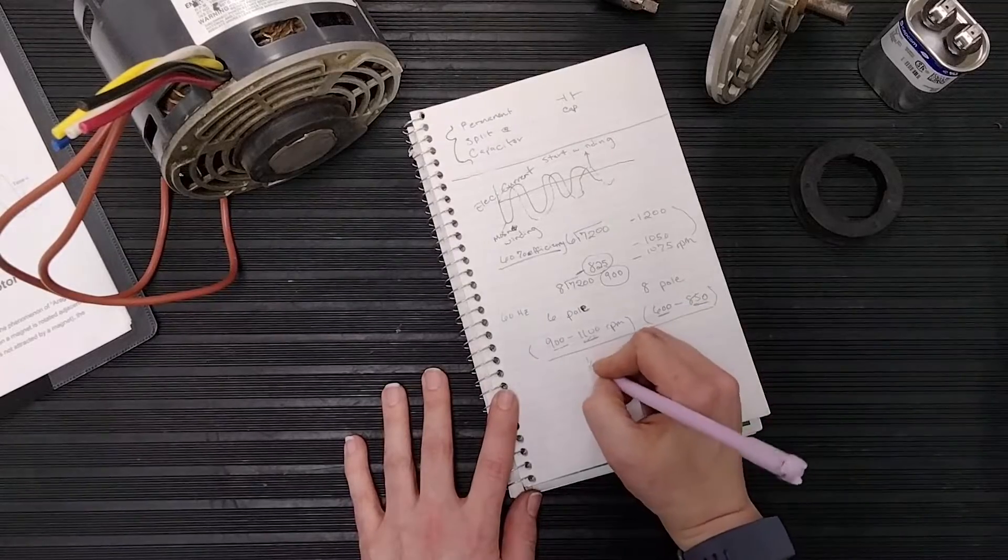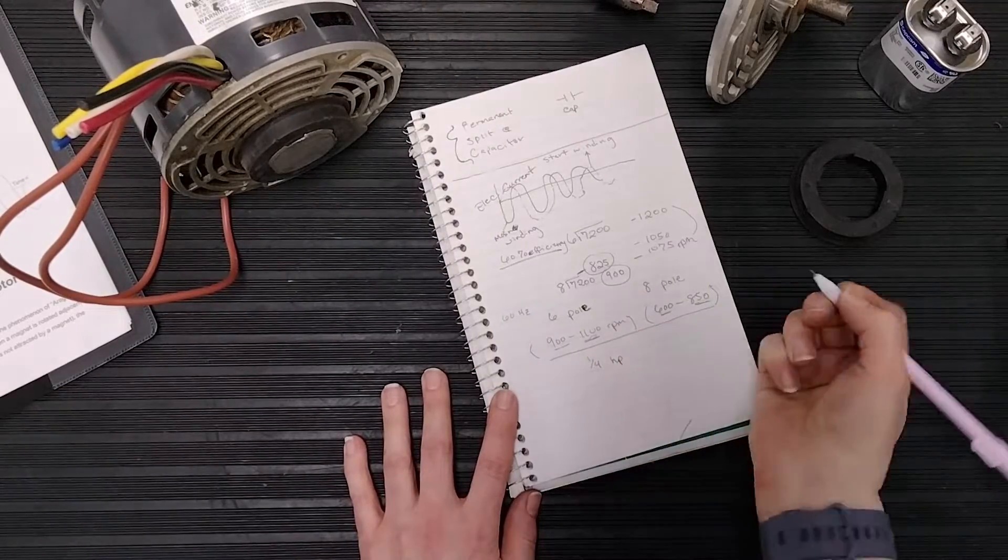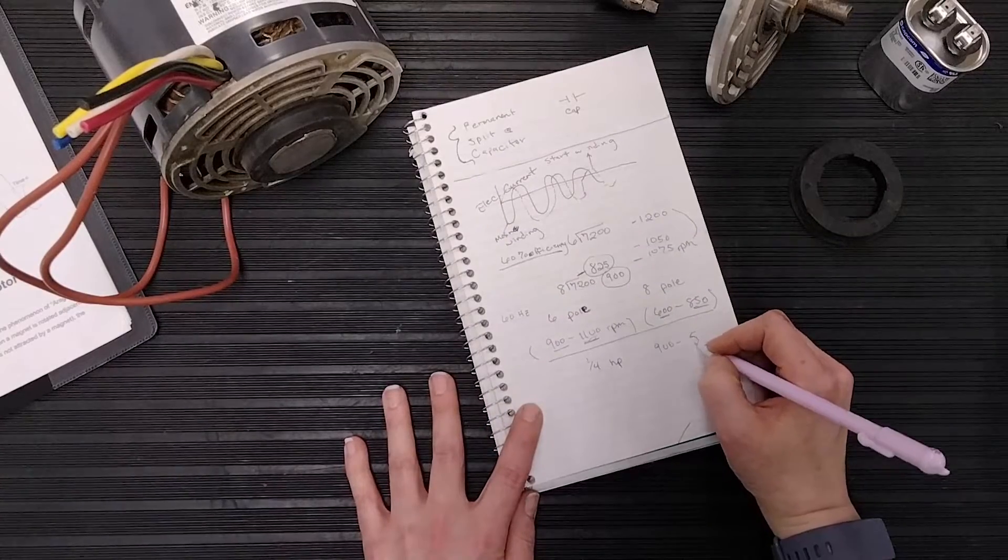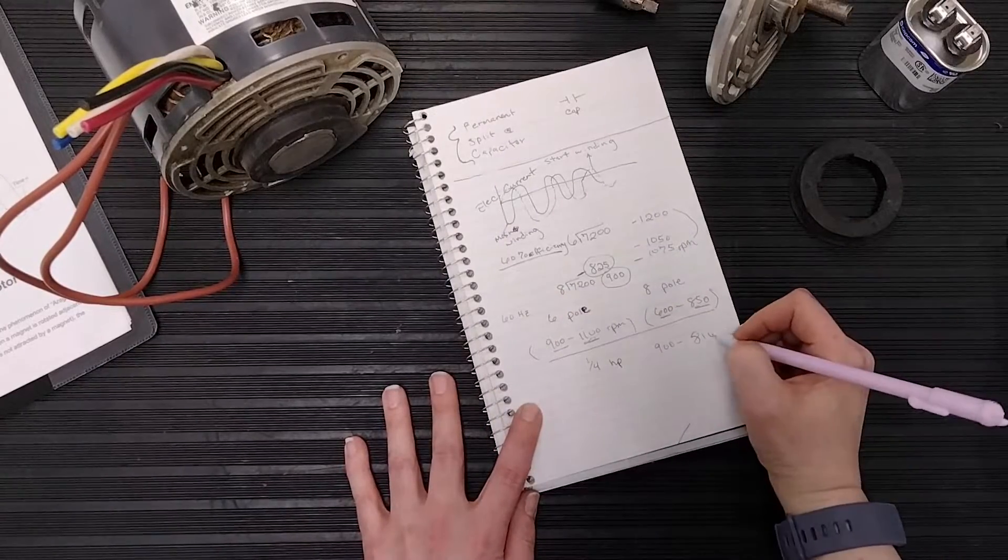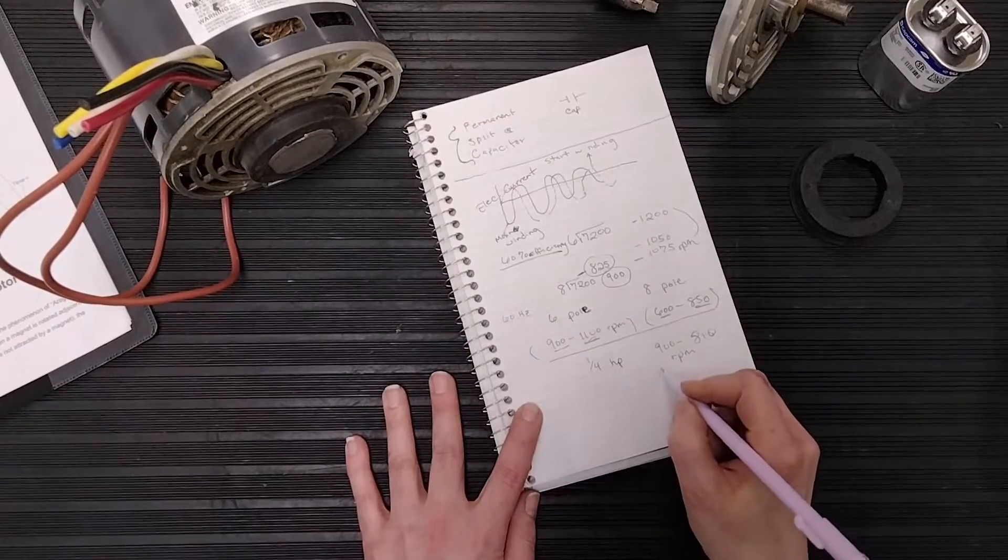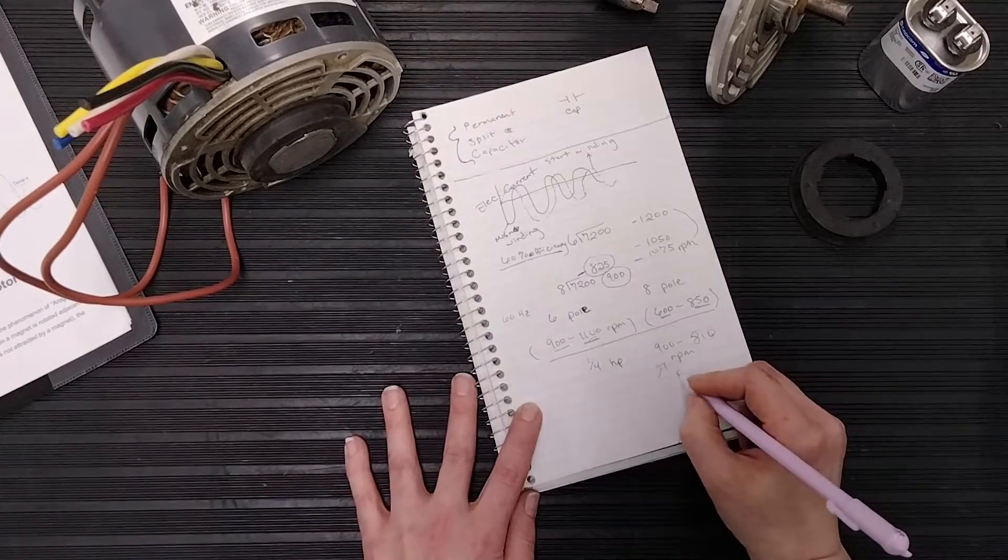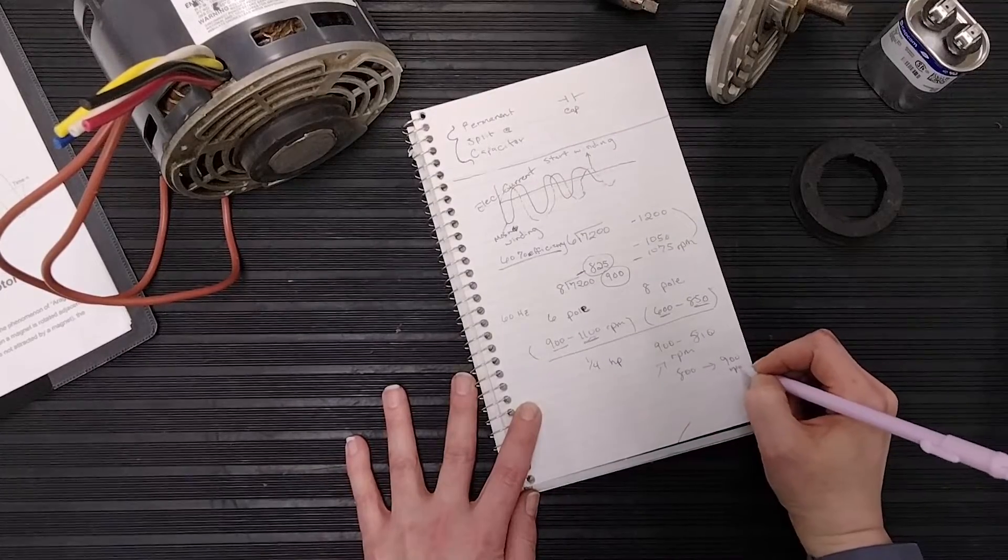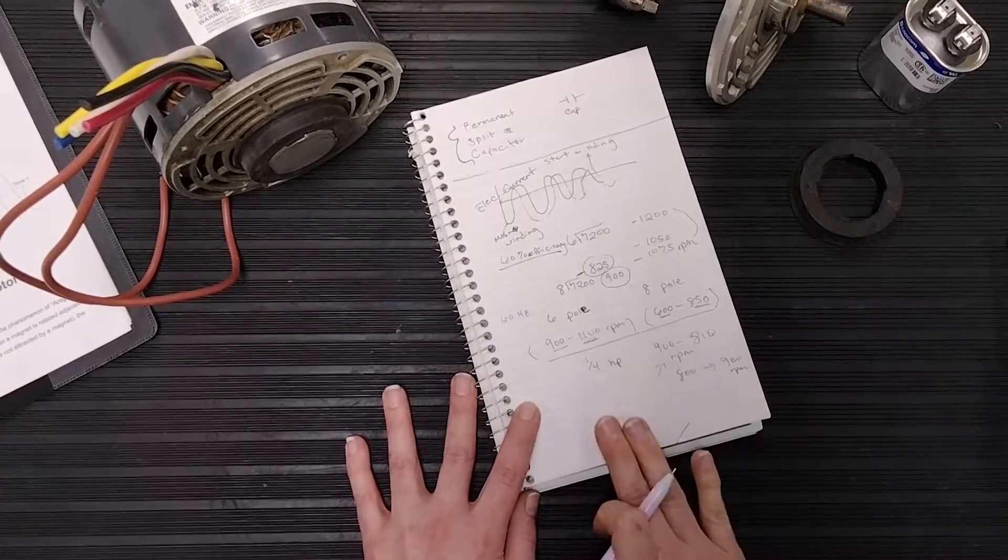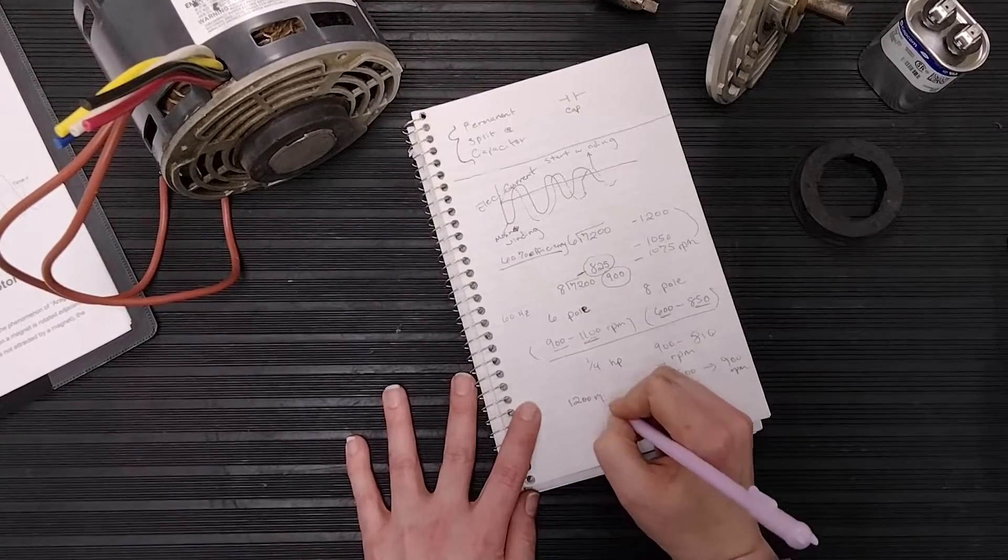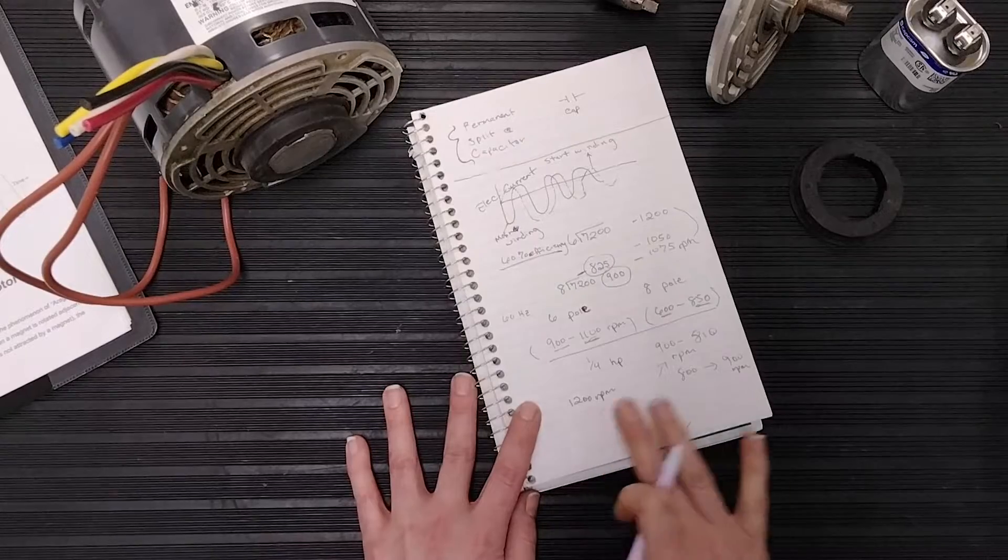Make sure that the specs line up. If yours is a quarter horsepower, somewhere between 900 to, I've seen even some motors that say 810 RPM, replace it with something that's going to be somewhere between 800 to 900 RPM. Same goes for those 1200 RPM motors.